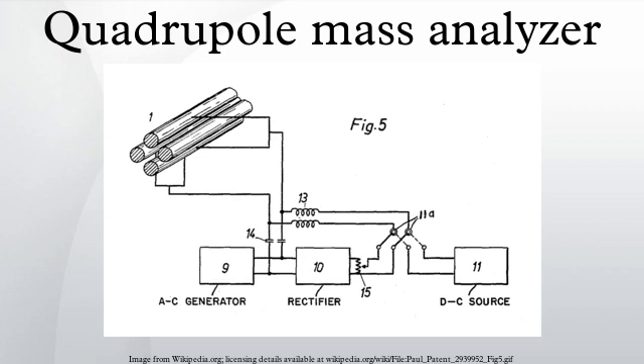A variant of the quadrupole mass analyzer called the monopole was invented by Von Zahn which operates with two electrodes and generates one-quarter of the quadrupole field. It has one circular electrode and one V-shaped electrode. The performance is however inferior to that of the quadrupole mass analyzer.